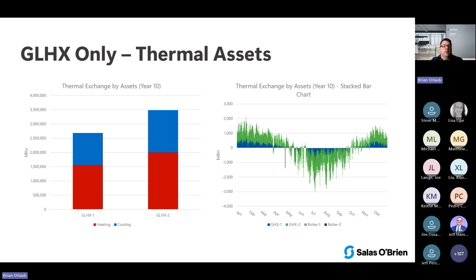Yeah, it works, you can do that. The boiler, if you manage it right, will provide enough energy to make it all the way around and hit the last building. But it takes a bit more energy, because you have to make sure the boiler energy isn't going into the ground. You have to maintain your ambient loop temperature less than your bore field supply temperature, or energy goes the wrong way. So you have to model all that and try to optimize it.